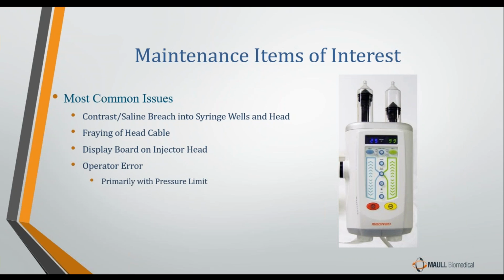The other most common issues, the display board on the injector head. And this is, again, pretty much universal of all contrast injectors, make, model, manufacturer, it doesn't matter. This is the display board on the injector head. On this one it's the Stellant. But this board gets beat up more than most other boards, pretty much on all the models, for two reasons. One, this is the board that the operator is touching and pushing buttons on and things like that. And this is also the board that's getting fluids spilled on it.